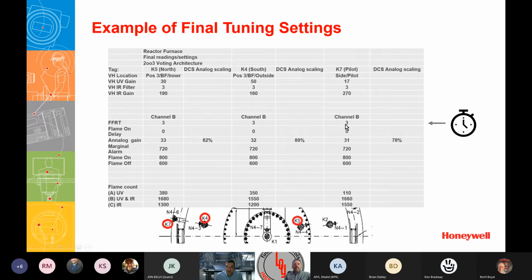If you put 0 here and put 3 here, I will guarantee you on this particular process, you will be calling me and I will ask you to send me your tuning map, and the first thing I'm going to change is these 2 variables. But the big point here is now we've taken care of the reliability and safety part and balancing the 2 things from frequent relights. I now added 3 seconds. This is the whole point of this part of this discussion. I have to do that in order to avoid what we just talked about.